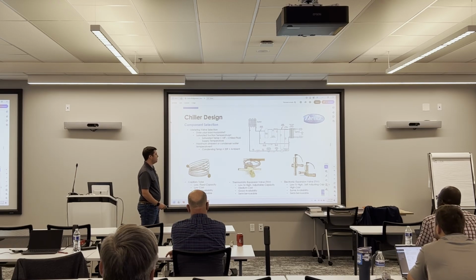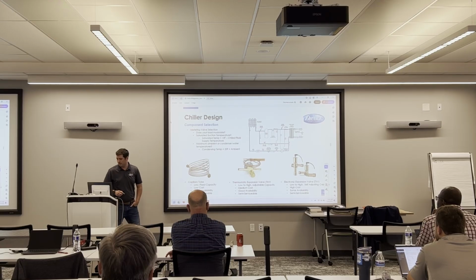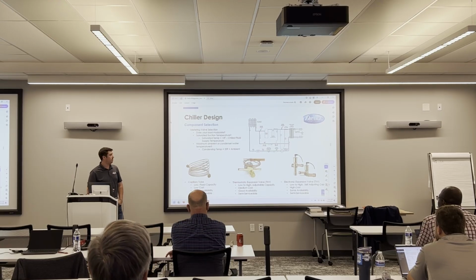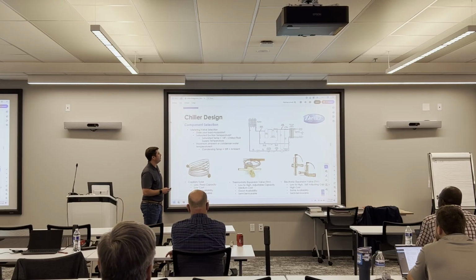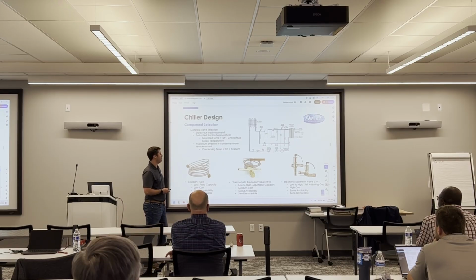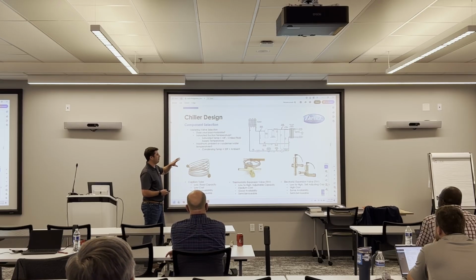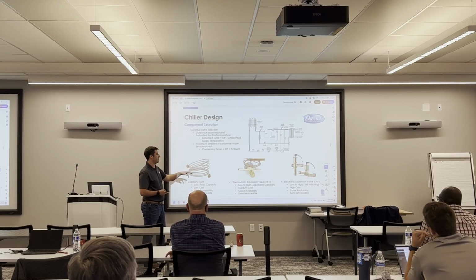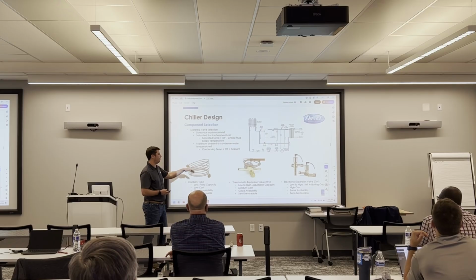And then the electronic version of that is an electronic expansion valve. I have a little typo there, I should say EXV. Low to high cost, self-adjusting, so we have some pretty sophisticated controls where we can calculate a real-time superheat calculation. So if you know your suction pressure and your suction temp, that's enough information to calculate the superheat. Our controller will send a command to the valve to control it to a desired superheat. So we'll say, I want the superheat to be 15 degrees.